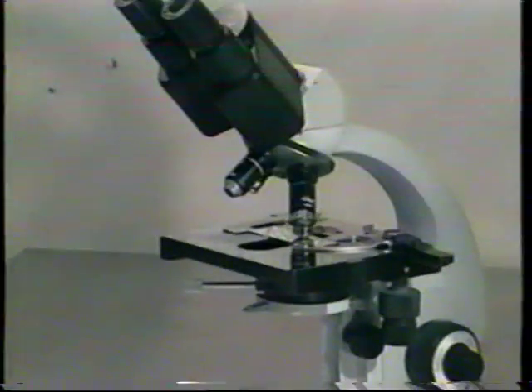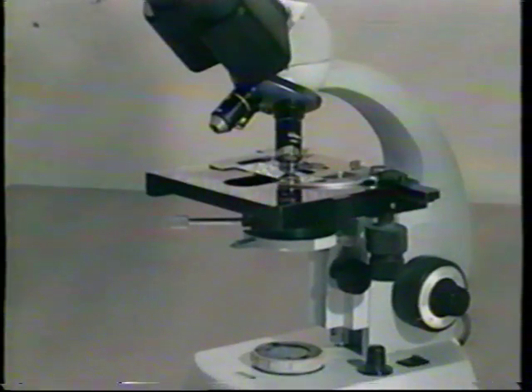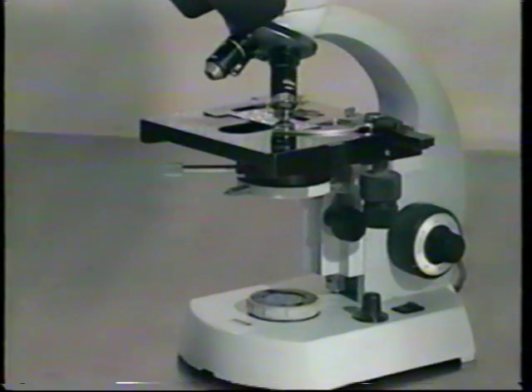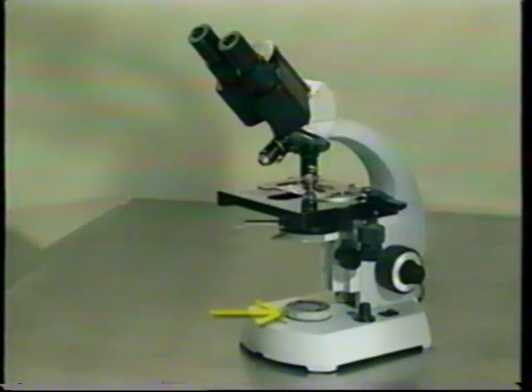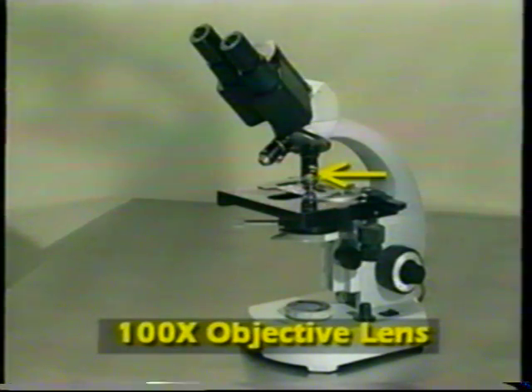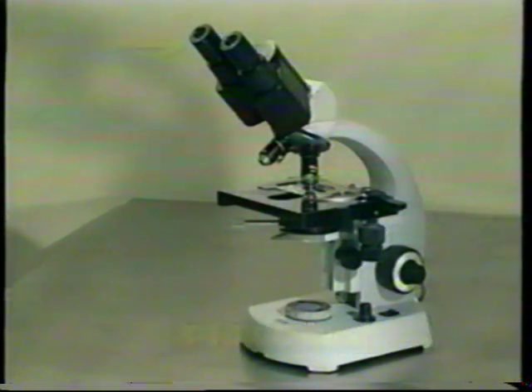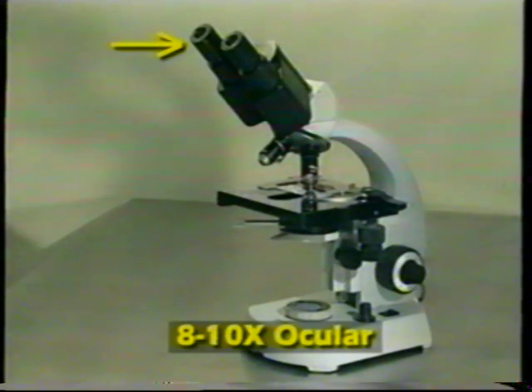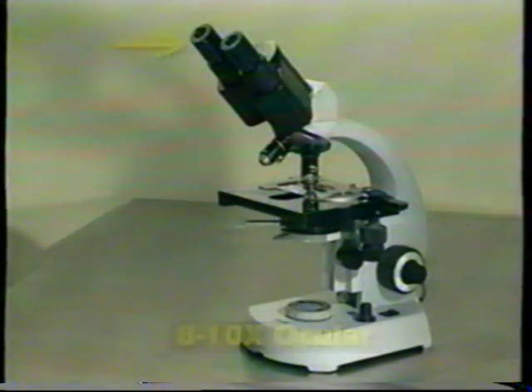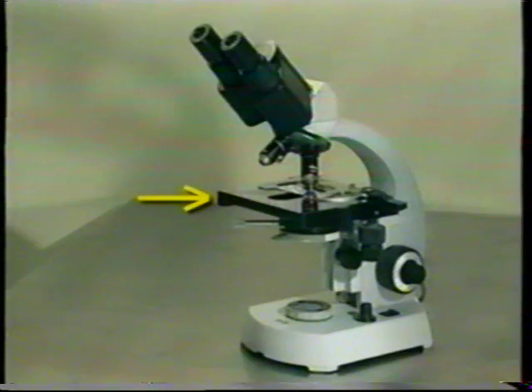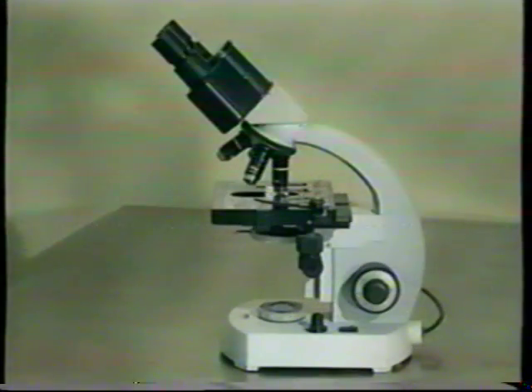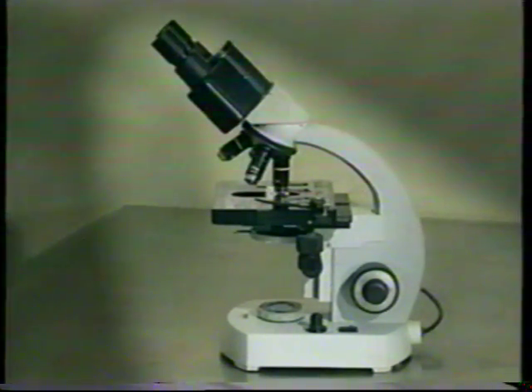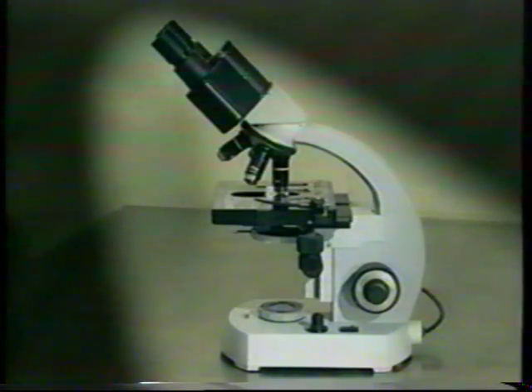A good quality binocular microscope is recommended for reading TB smears. It must be equipped with an electrical light source or mirror, an oil immersion or 100x objective, eyepieces of 8 to 10x magnification, and a mechanical stage. Daily care and cleaning are essential to avoid dust, oil buildup, and moisture.